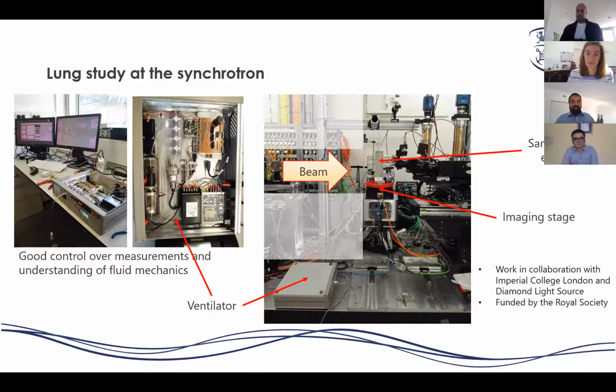There's going to be all of this sort of movement of the gas, compression. We need to account for these compliances in the system. So good knowledge of fluid mechanics will allow us to calculate this to create a suitable pumping device. Then the mechanical engineering side of me had to come up with a way of putting this into a nice housing, designing that all appropriately. We're now integrating sensors to monitor pressure. We're using solenoid valves to not pop the lungs and things like this. So all of this needs some good knowledge of electronics to wire it all together. And then there's the coding side. We need to control the pump in a suitable way so that we can inflate and deflate our lung accordingly.